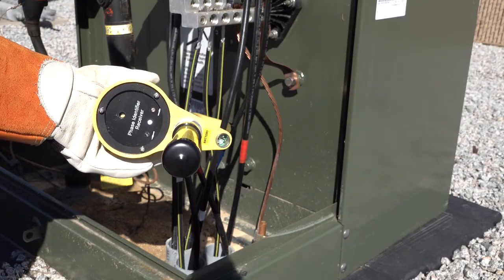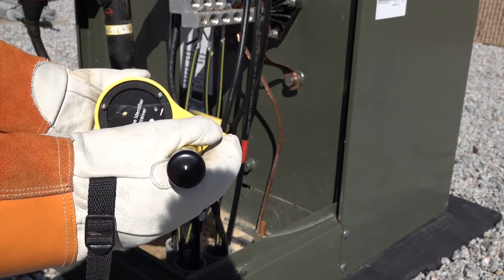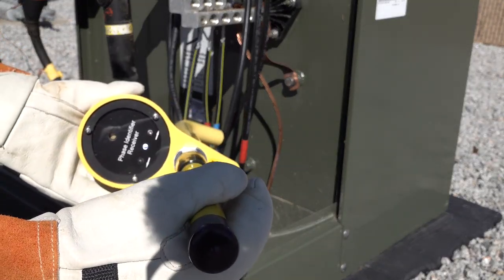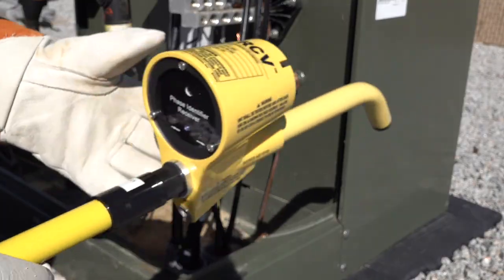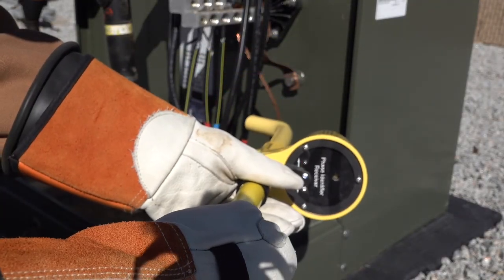If you recall from our earlier example, this is the same conductor that we were attached to with the red lead. So not only have we identified a conductor that the ST800 is attached to, but we have identified which lead the red conductor of the ST800 is attached to, which just so happens to be the hot conductor. We can verify our connection by testing the other hot conductors, that there is no pulse on those as well, but only the conductor we're attached to with the ST800.